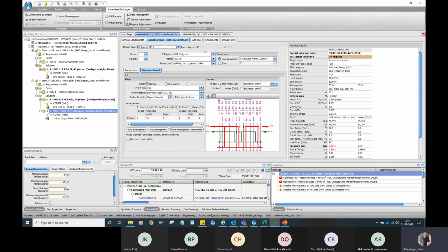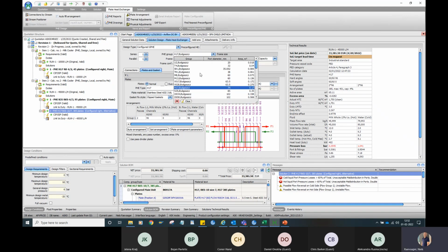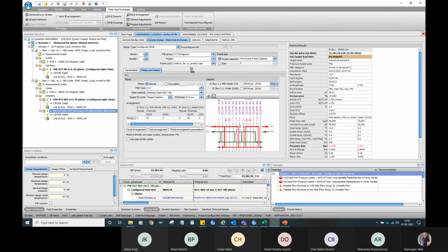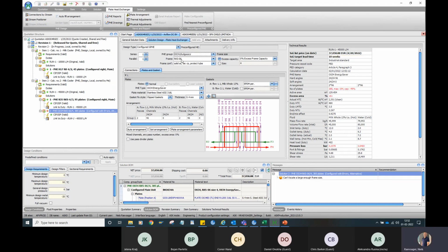Then we could try to change the H17 to an 034, which Alexandra had, and I believe it was Bojan. So we change it to an 034. In a 6-bar version, it comes up with 0.4 millimeter plates. That's not good, we want 0.5 as a minimum for food applications.